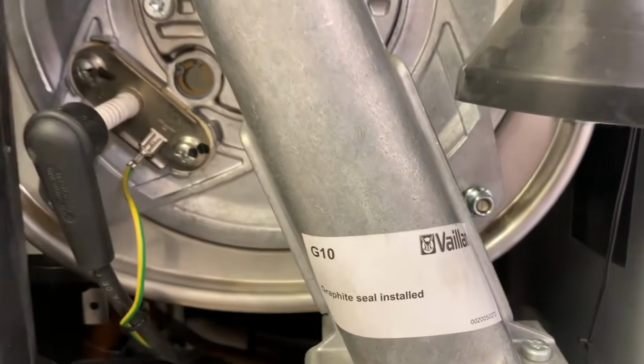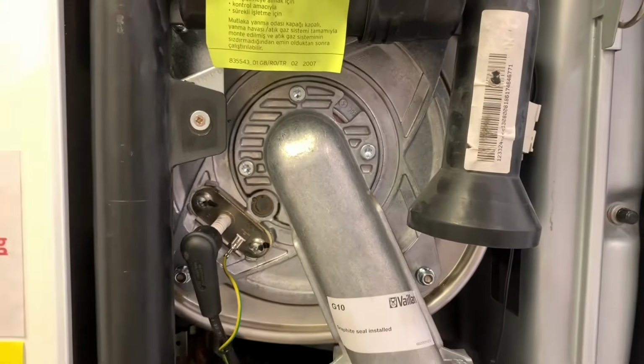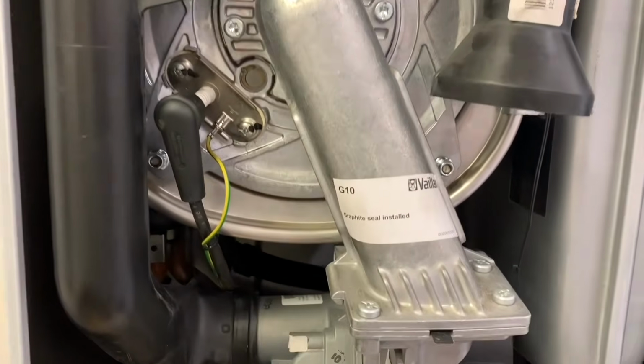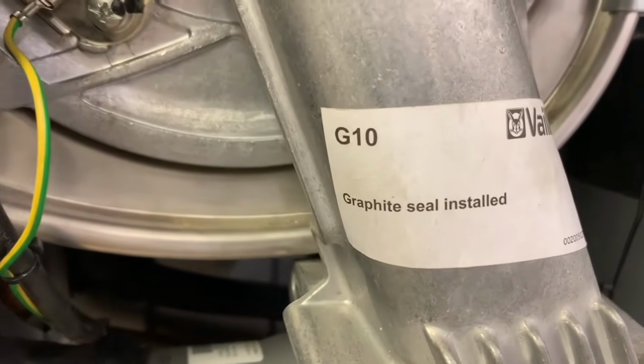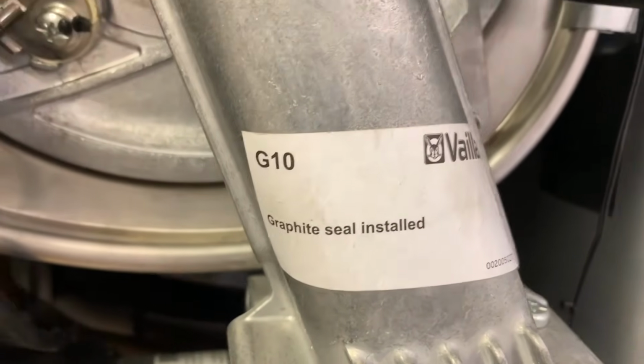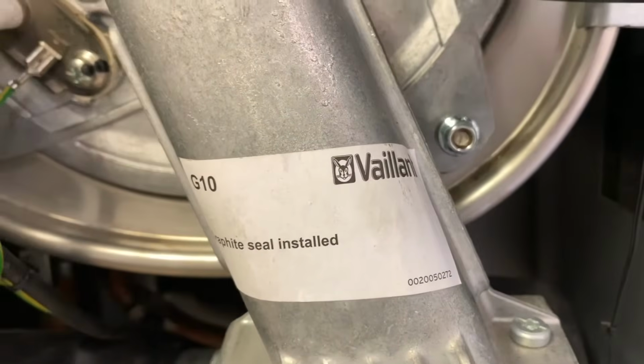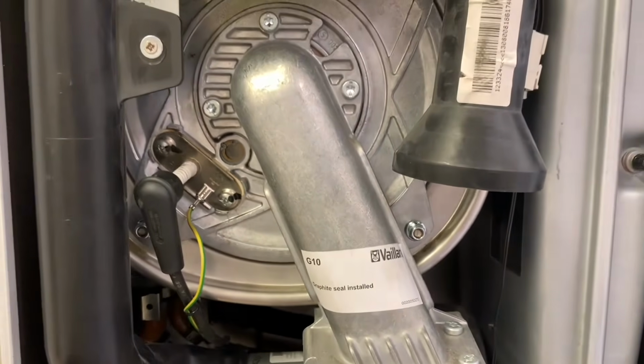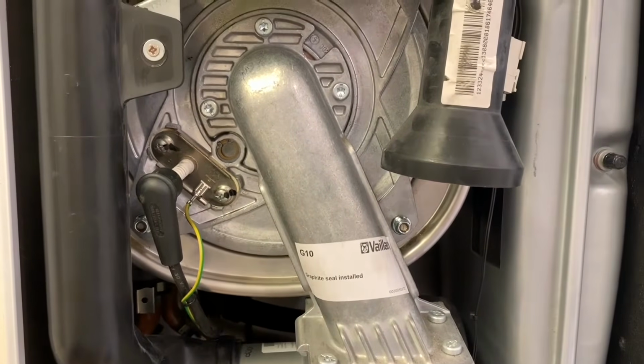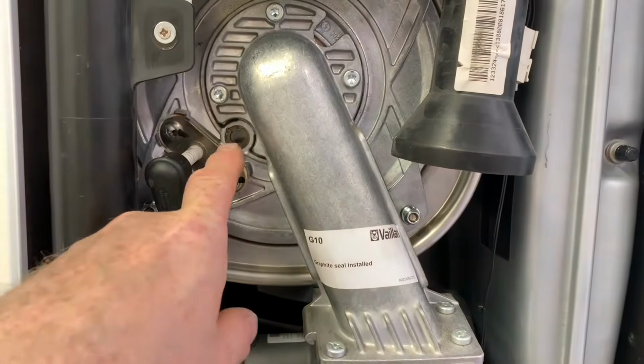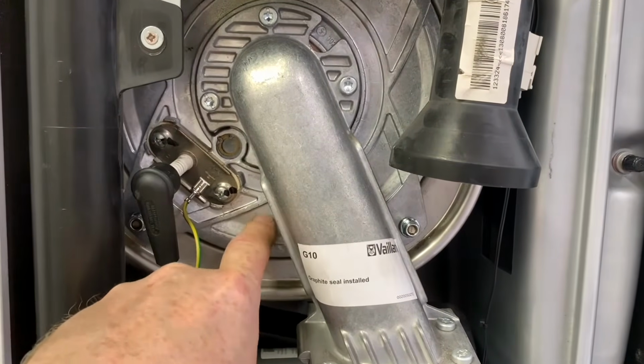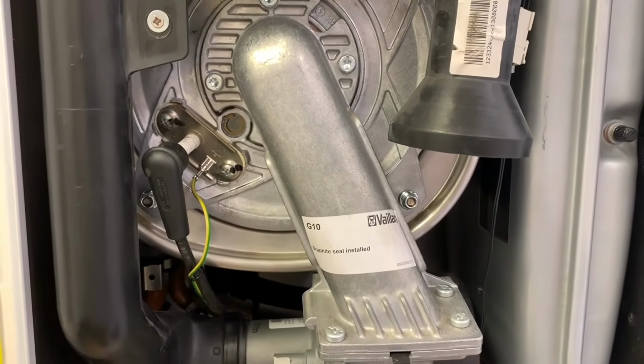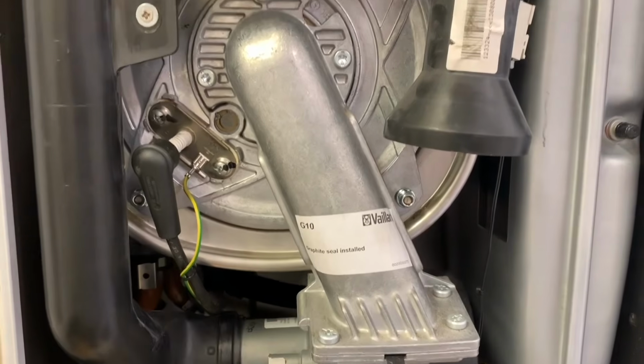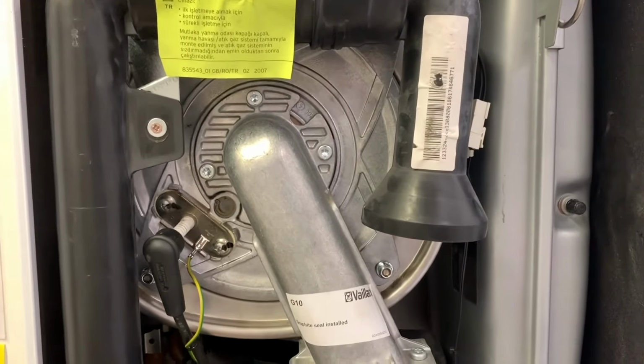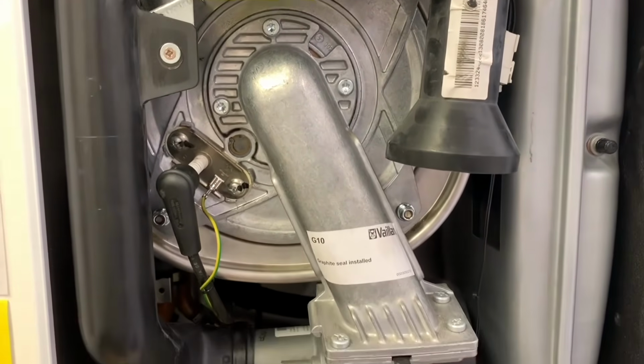which tells us the burner gasket seal, which we'll have a look at again closer when we take it out, has been replaced. But for some reason, like I say in the other video, nobody writes any dates on it when it was changed. According to the manufacturer, for the first 5 years, we don't need to take this burner cover off. Then after that, it's annually. And the gasket will need to be changed if we ever take this door off. But like I say, we'll have a look at that later.